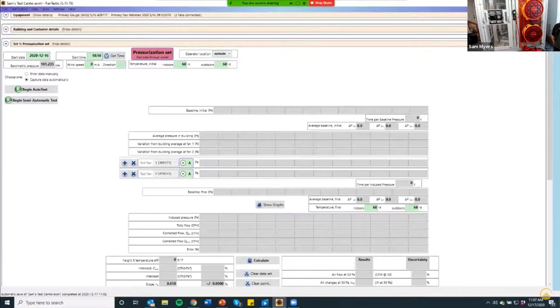Let me move that. But usually what I like to do is what's called the semi-auto test. And that just allows you to customize the test parameters a little more. So if I wanted to start up at 60 and go down in increments of 10, I can tell it to do that. Auto test is going to go up to like 65 and go down like 8.5 each time. It'll take 12 baseline readings. But another thing about the semi-auto is I can stop and start the test whenever I want without screwing anything up. I can pull this gauge view over to the side.